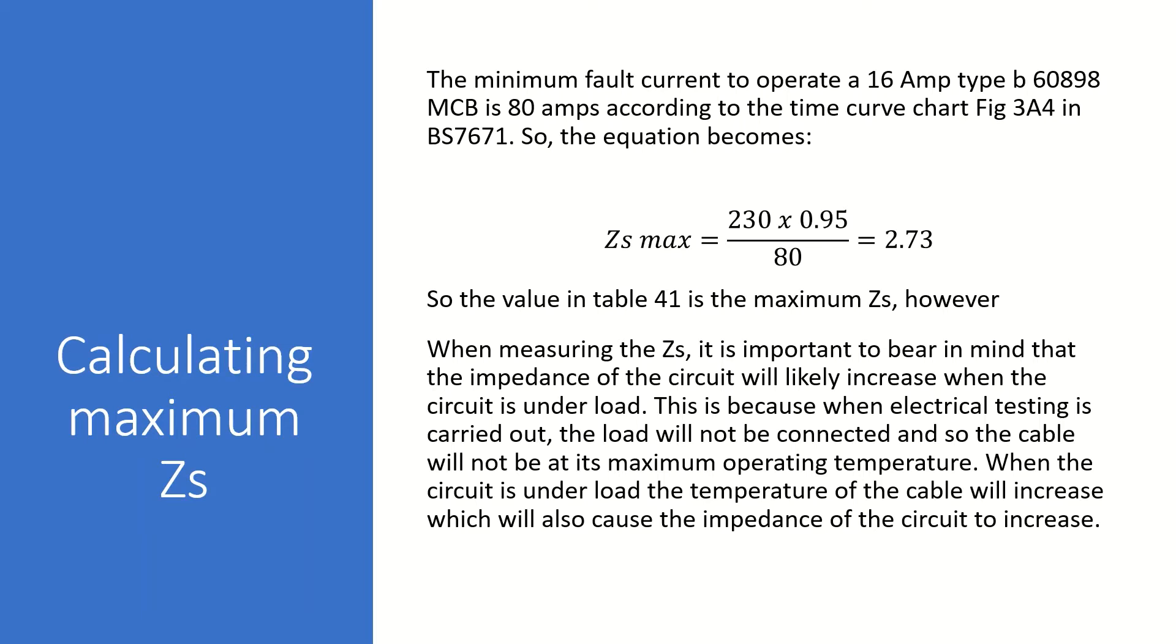However, when measuring the Zs, it is important to bear in mind that the impedance of the circuit will likely increase when the circuit is under load. This is because when electrical testing is carried out, the load will not be connected, and so the cable will not be working at its maximum operating temperature. When the circuit is under load, the temperature of the cable will increase, which will also cause the impedance of the circuit to increase.